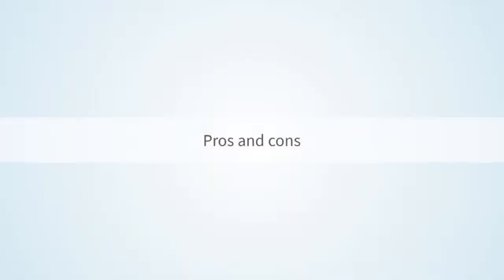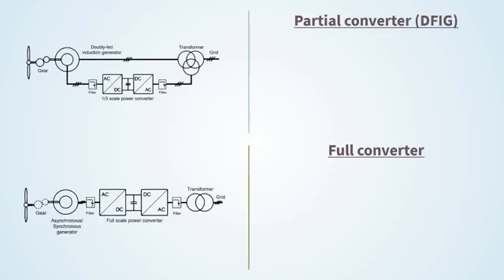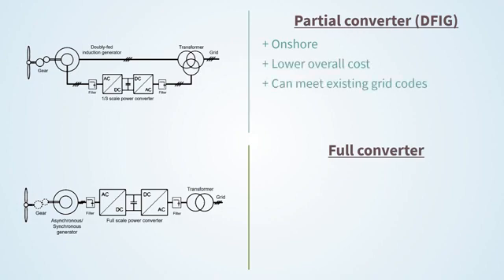Let's now focus on the pros and cons of both converter topologies. On the one hand, the doubly fed induction generator is mainly used on onshore wind turbines. The overall wind turbine cost is lower and can meet existing grid codes. However, maintenance is more expensive and turbine power levels are limited to a maximum of six megawatt at present.